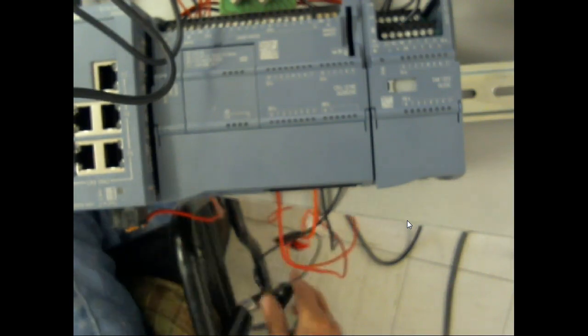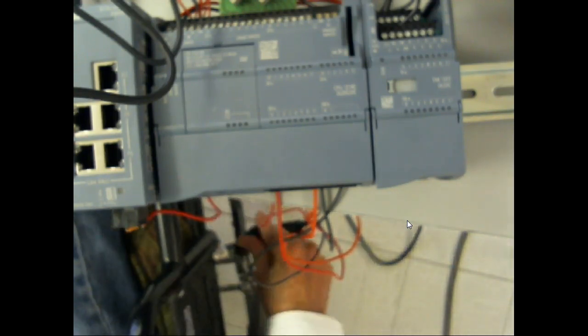We have different ways we can send information. We can send it by using voltage levels, right? You understand? Or we can send it using current levels. There's a technique out there called the 4 to 20 milliamp current loop, which is very popular in industry because it's really immune to noise, electromagnetic interference. So if this thing right here generates a magnetic field, and I've got a piece of wire right up against it, and that magnetic field cuts through that wire, it's going to try to generate a voltage into the wire right beside it. We call it EMI, electromagnetic interference.